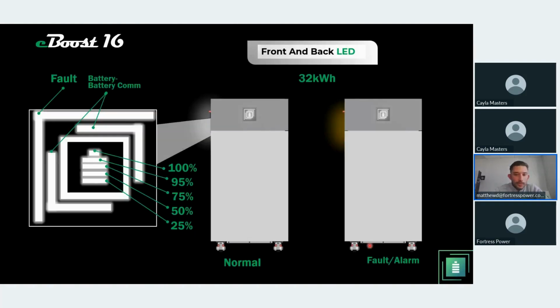So the battery itself has 2 indicators, right? You have the front LED. The front LED gives you, starting from the bottom bar, a 25% state of charge indicator, then 50%, 75%, 95%, and that little dot is 100%, right? Then you have an outer frame, which lets you know if there's battery-to-battery communication. If there is, both of those will be lit up, right?